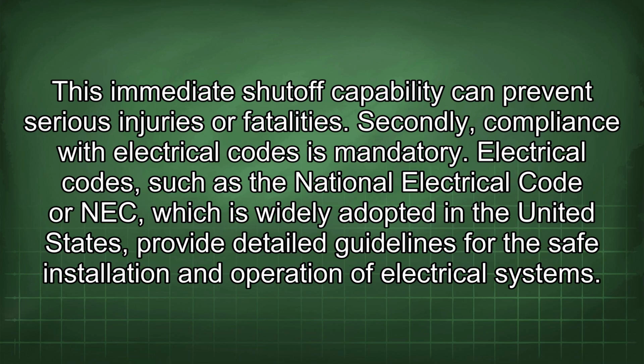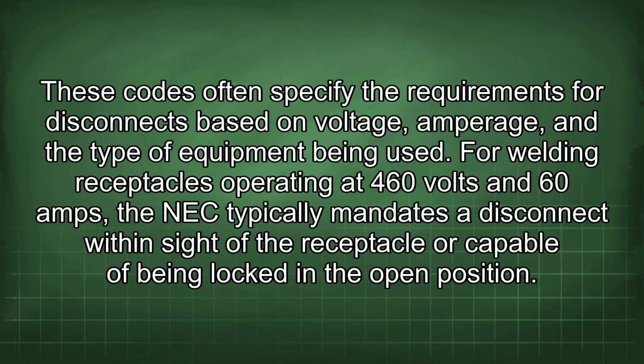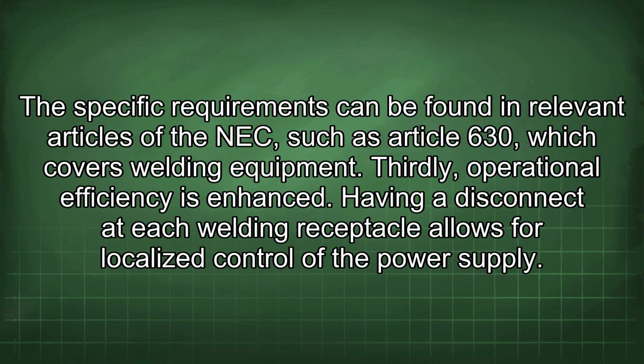Electrical codes, such as the National Electrical Code or NEC, which is widely adopted in the United States, provide detailed guidelines for the safe installation and operation of electrical systems. These codes often specify the requirements for disconnects based on voltage, amperage, and the type of equipment being used. For welding receptacles operating at 460 volts and 60 amps, the NEC typically mandates a disconnect within sight of the receptacle or capable of being locked in the open position. The specific requirements can be found in relevant articles of the NEC, such as Article 630, which covers welding equipment.